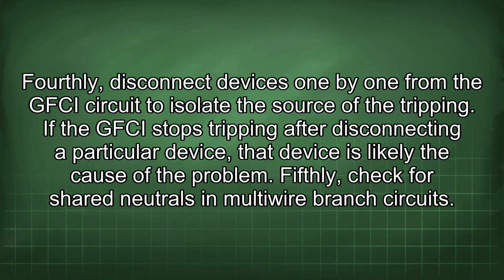Fourthly, disconnect devices one by one from the GFCI circuit to isolate the source of the tripping. If the GFCI stops tripping after disconnecting a particular device, that device is likely the cause of the problem.